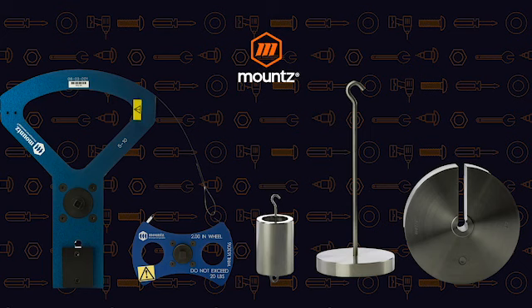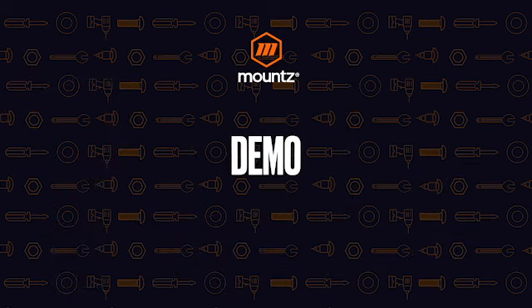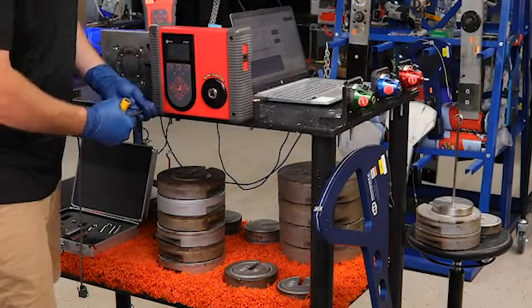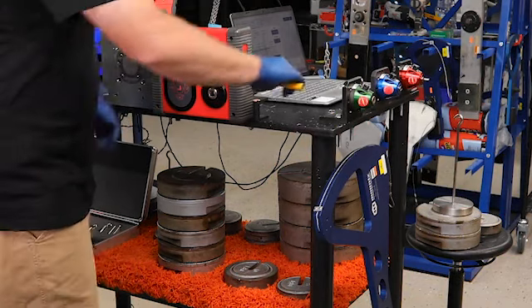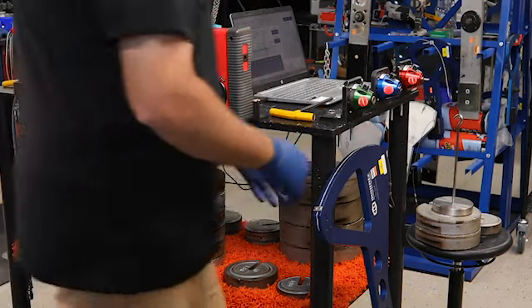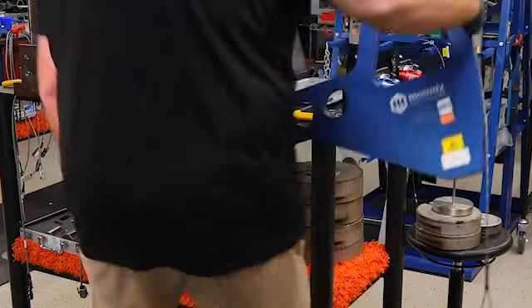But these are the calibrated weights that are used as part of the traceability that go into the actual list of the traceability if you were to run that from a specific tool. That tool then is traceable to the analyzer, and that analyzer eventually is traceable to the actual weights, which are, again, accurate and calibrated to their specific weight. So let's go ahead and look at the demo that we have. And this, again, is an LTT 200 F, or 200 foot-pound sensor. And we'll use the 2-foot segment arm.